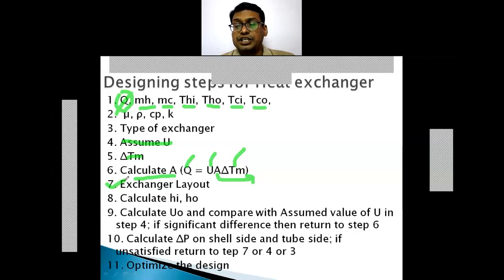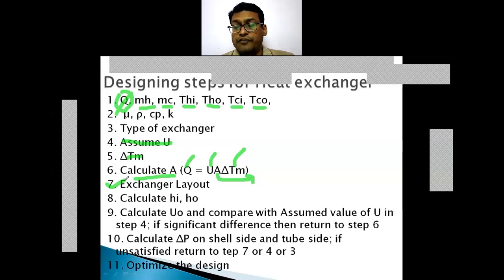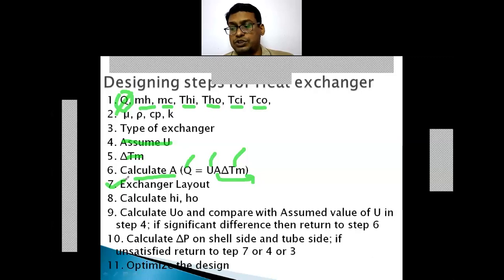The next step is to calculate the shell-side heat transfer coefficient h_o. For this, one must calculate the flow area for the shell side — that is, the heat transfer area on the outside of the tubes. Then calculate the velocity of the fluid passing through the shell side, the equivalent diameter for the shell side, the Reynolds number for the shell-side fluid, and the Prandtl number. Finally, the shell-side heat transfer coefficient h_o is calculated using defined correlations in terms of Reynolds number and Prandtl number.